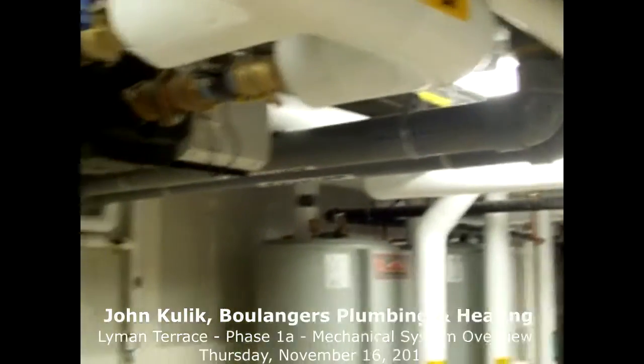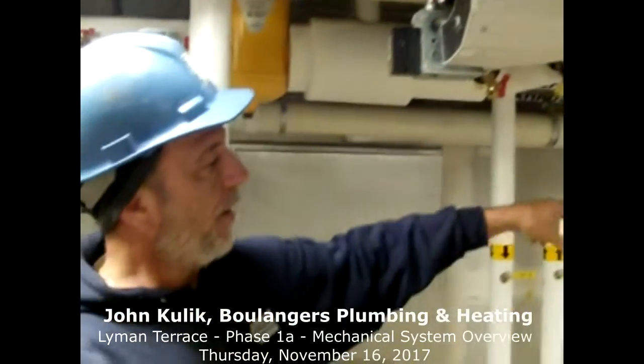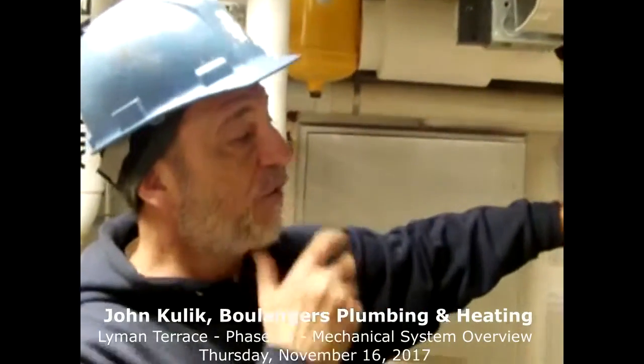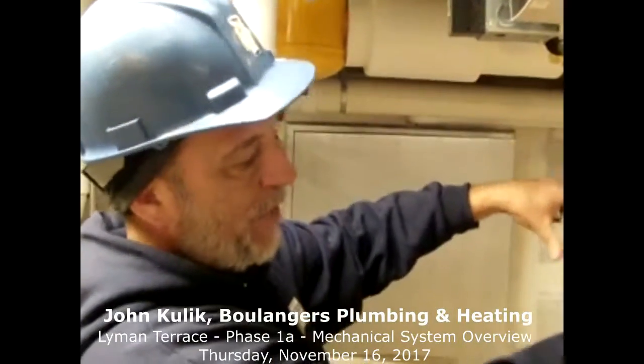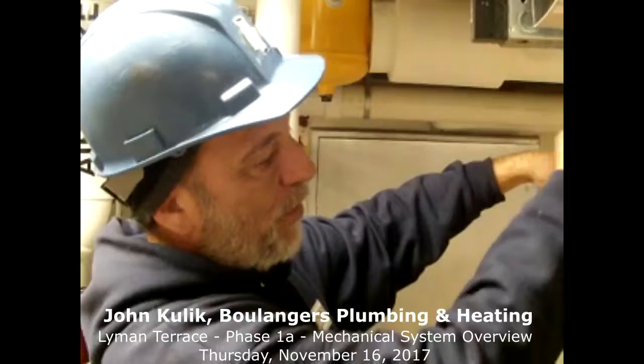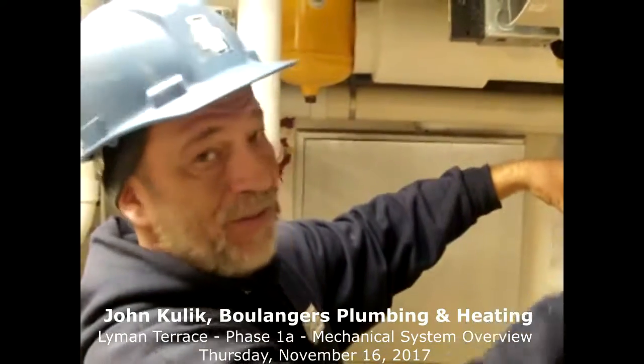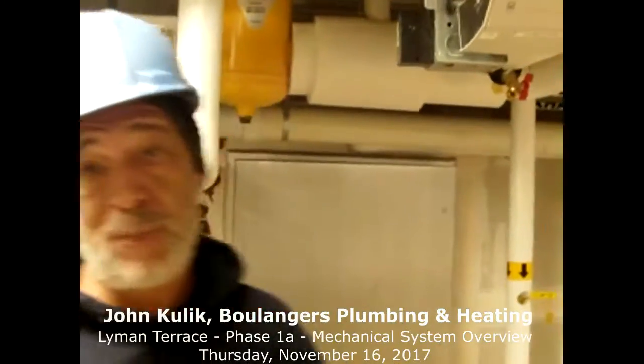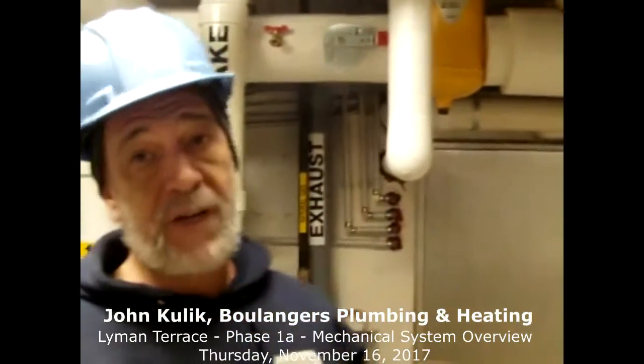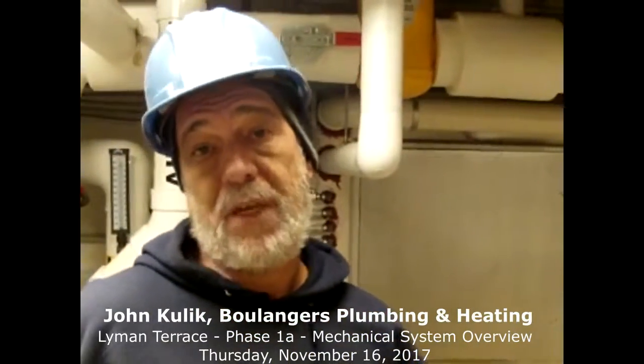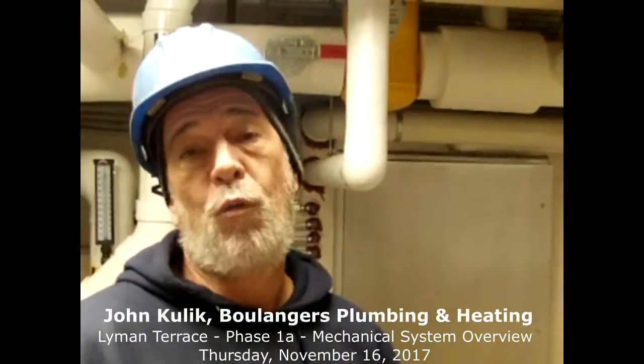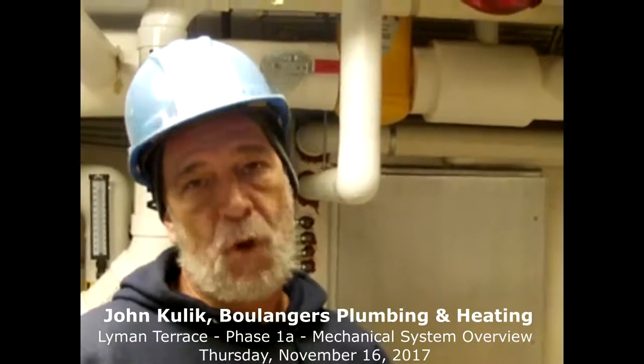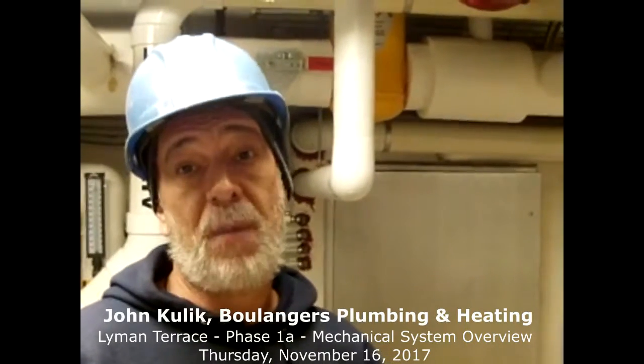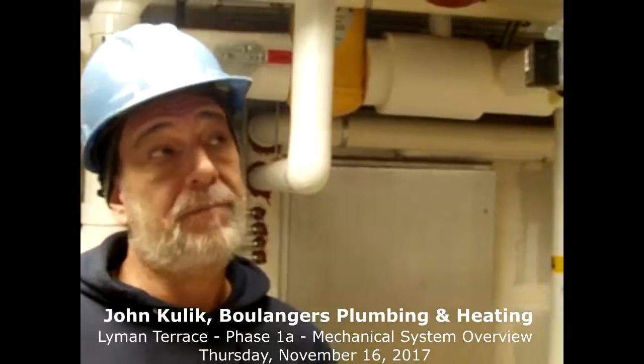The first tank is what they call a buffer tank. It doesn't have any water coming out of it to go to the mixing valve. It's preheated, so when they do start flowing, the water comes out of that one into the next one for efficiency purposes. It also helps the boiler continue to make condensation, because the boiler likes to have cold water coming back to it. It's most efficient when it has cooler water coming back.